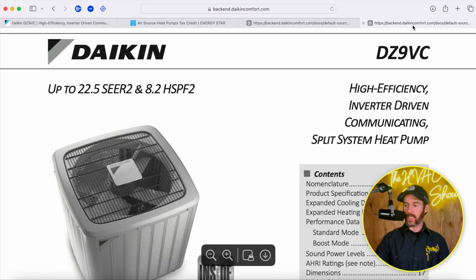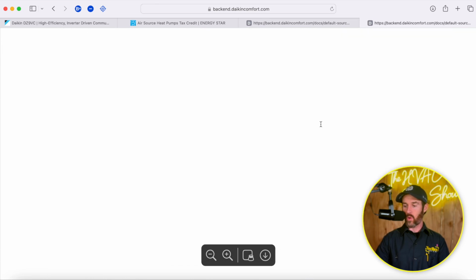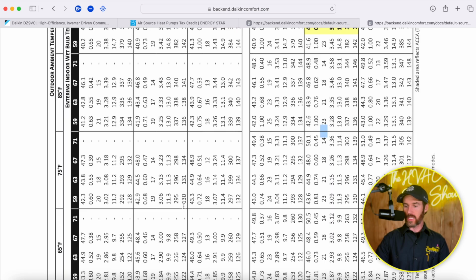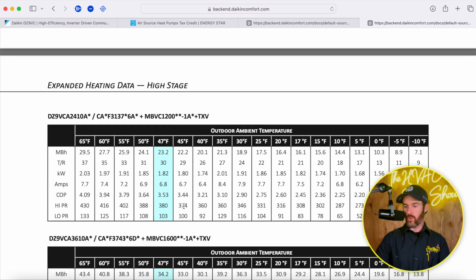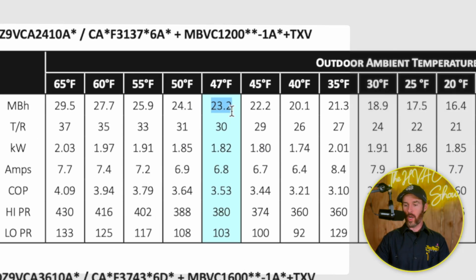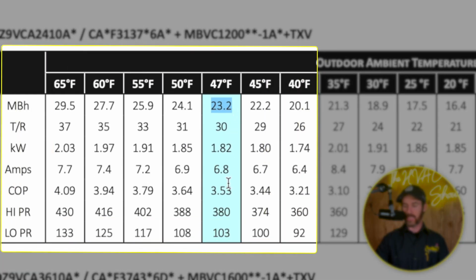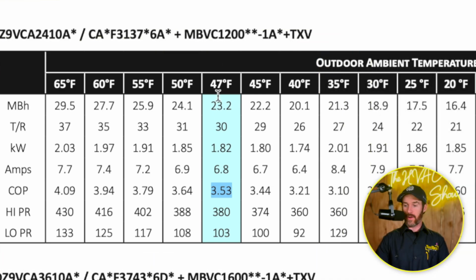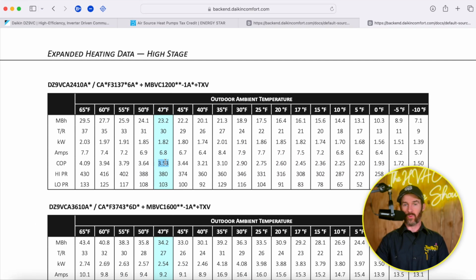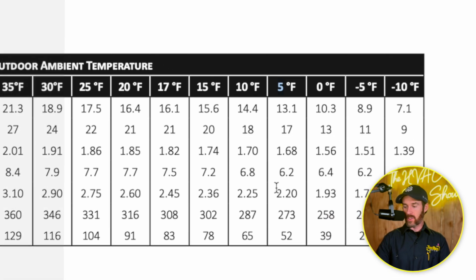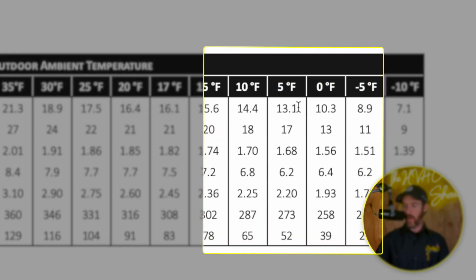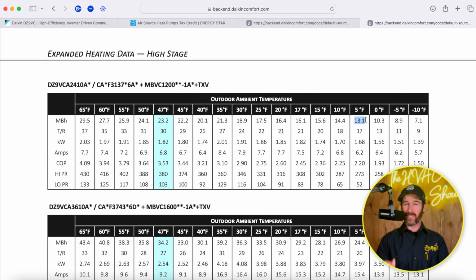And if you look at the DZ9 and we scroll down to the same cold climate data, the heating performance data, on the 2-ton system, right here, same thing, 23.2 thousand BTUs is the output. The COP is a little bit more efficient at 47 degrees Fahrenheit, with a COP of 3.5. And at 5 degrees Fahrenheit, the COP is still more efficient, at 2.2. However, the capacity loss is such that it's 3,000 BTUs less than its Daikin Fit equivalent, which is pretty substantial on a smaller system like this. And so that's why the Daikin Fit qualifies in those cold climates, but the DZ9 does not.